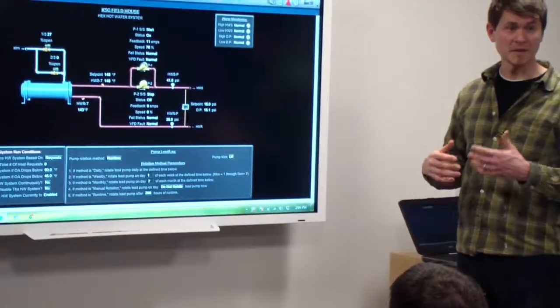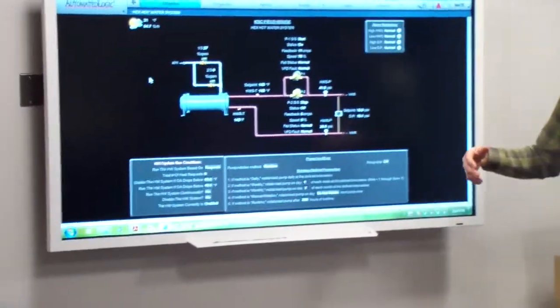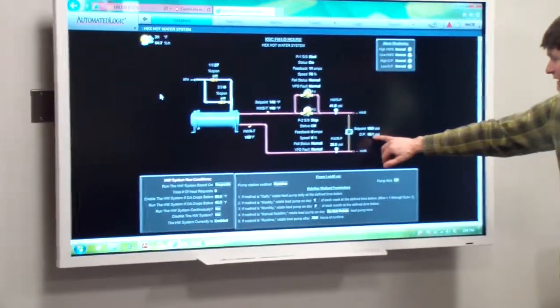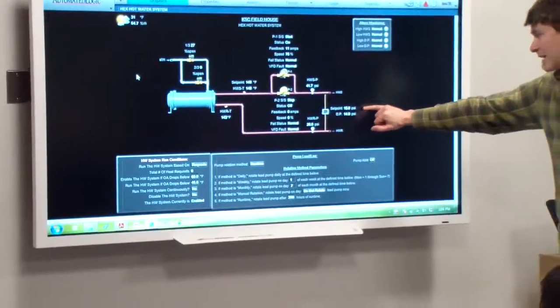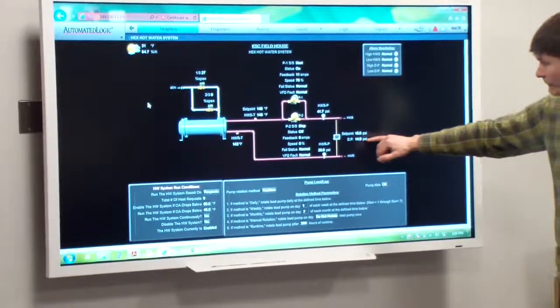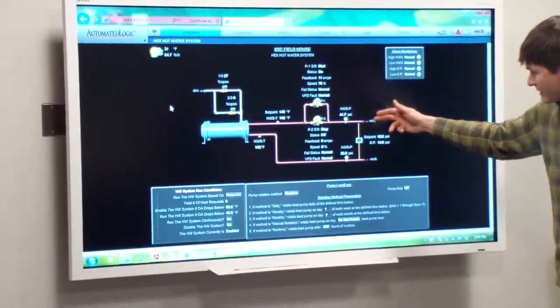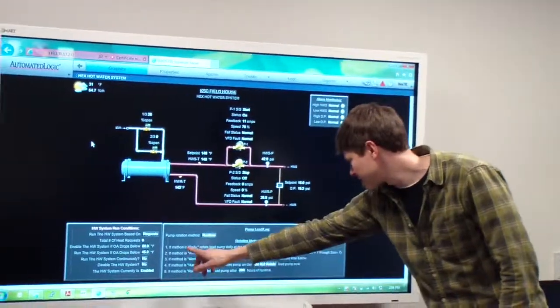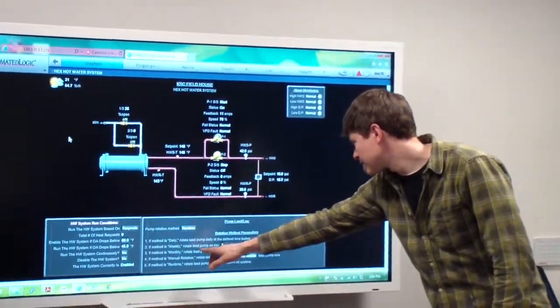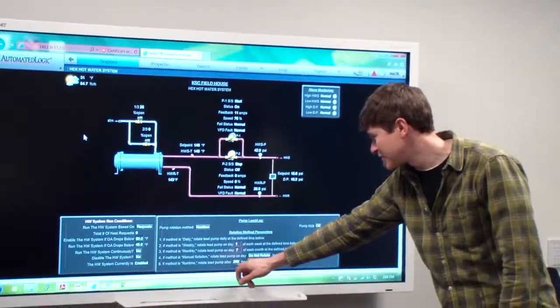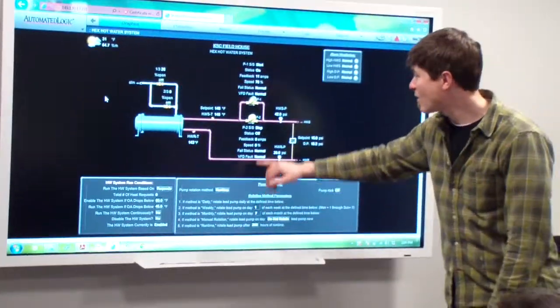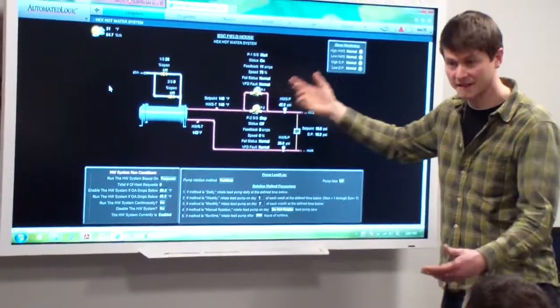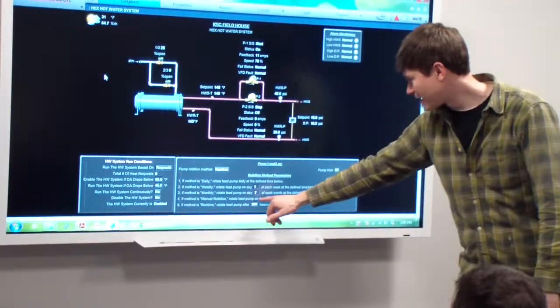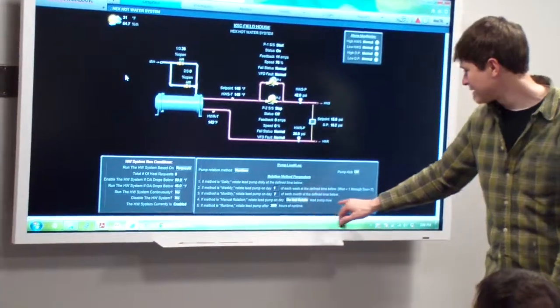The secondary pump will pick up the slack, and you will get an alarm back at the front end. This is running based off of a DP balancer set point, which is 15 pounds. And you'll see that's the difference between your supply and your return. And then actually it says right here, right now we're running based off a runtime, which is at 200 hours. So every 200 hours that this pump sees that it's running, then it's going to switch to the next one. You can do a manual rotation method, and we also have this pump kick function.